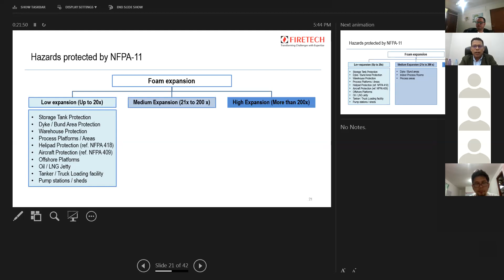Now coming to medium expansion foam systems, where the expansion value ranges from 21 times to 200 times. These are majorly used for dike areas, for indoor process rooms and process areas. And the high expansion foam systems are where the expansion is more than 200. It is majorly used for LNG and LPG tank dikes.